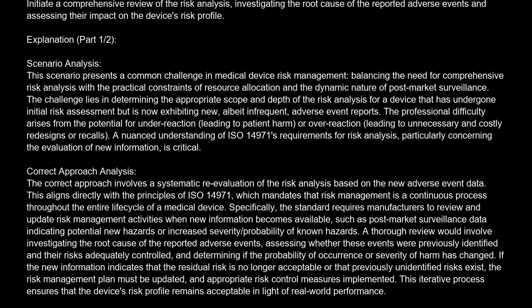The challenge lies in determining the appropriate scope and depth of the risk analysis for a device that has undergone initial risk assessment, but is now exhibiting new, albeit infrequent, adverse event reports. The professional difficulty arises from the potential for underreaction, leading to patient harm, or overreaction, leading to unnecessary and costly redesigns or recalls. A nuanced understanding of ISO 14971 requirements for risk analysis, particularly concerning the evaluation of new information, is critical.